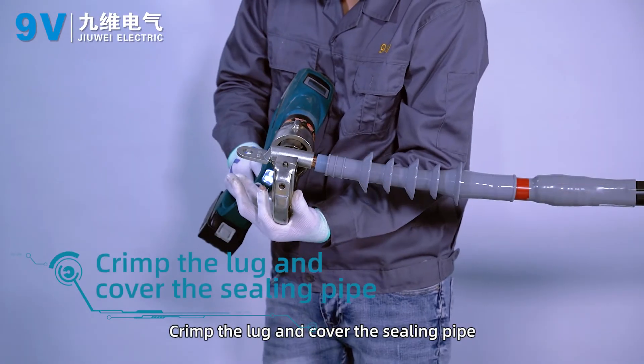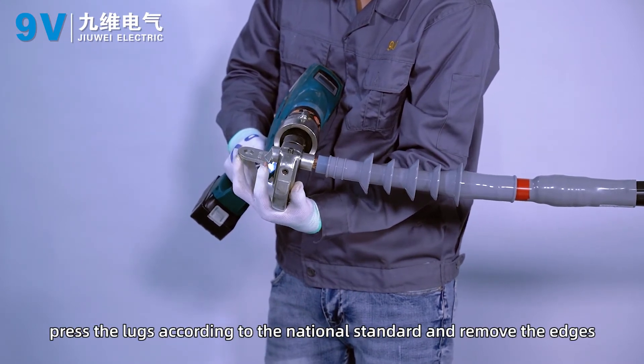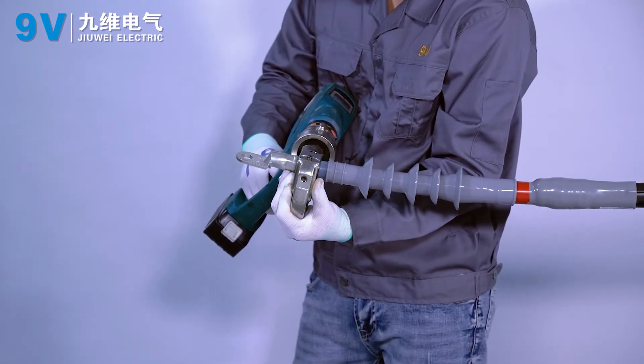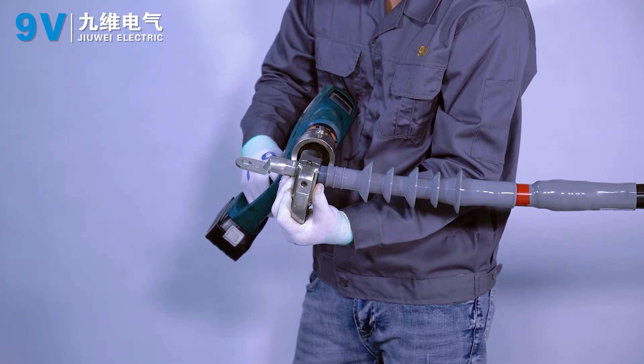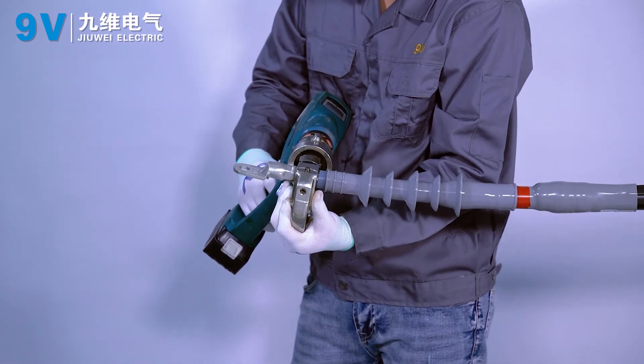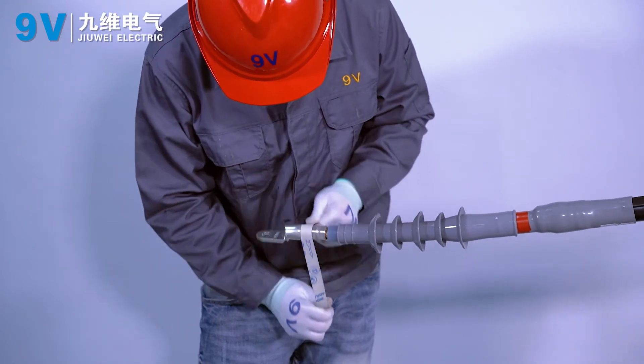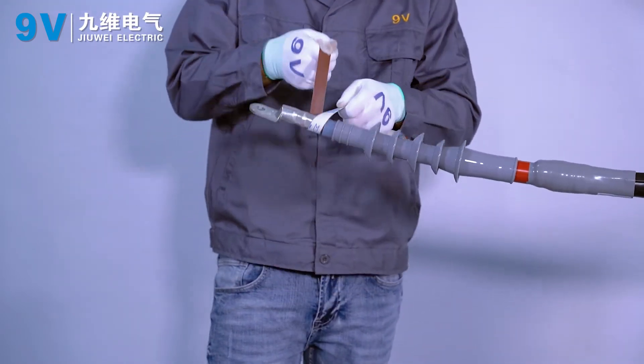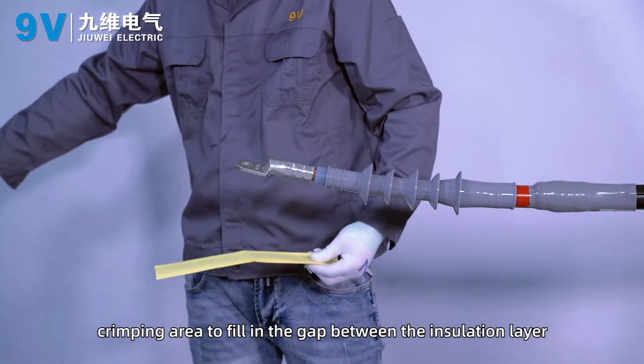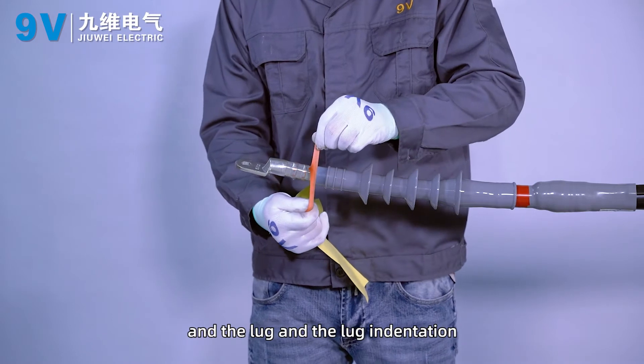Crimp the lug and cover the sealing pipe. Cover the lugs and press them according to national standards, then remove any edges and burrs from the lug. Wrap sealant around the wiring lug crimping area to fill the gap between the insulation layer, the lug, and the lug indentation.